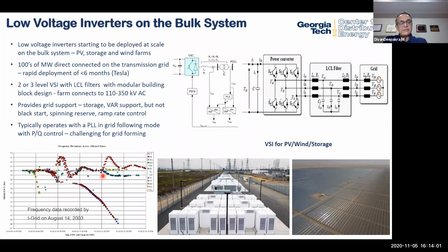You can start seeing that you have very significant dynamic frequency deviations that occur when you have big faults on the system. And your inverters, how do they react to that? If you actually have a black start capability or requirement, how do the inverters do that? That's a grid-forming inverter versus a grid-following inverter. And we have all these requirements where we really haven't moved very far in terms of how we control and operate our systems.